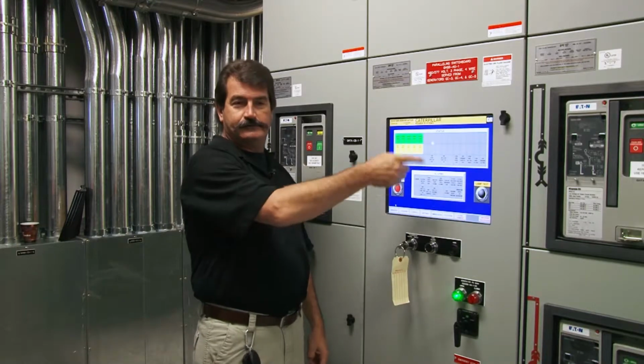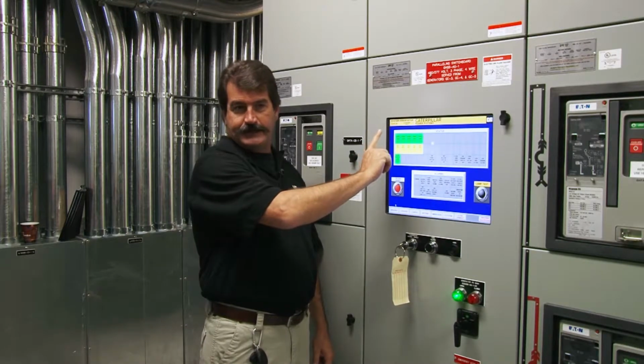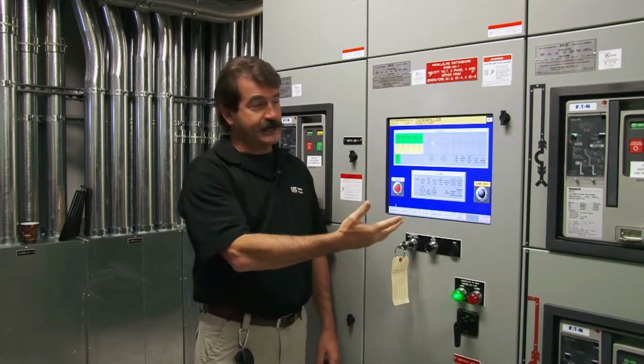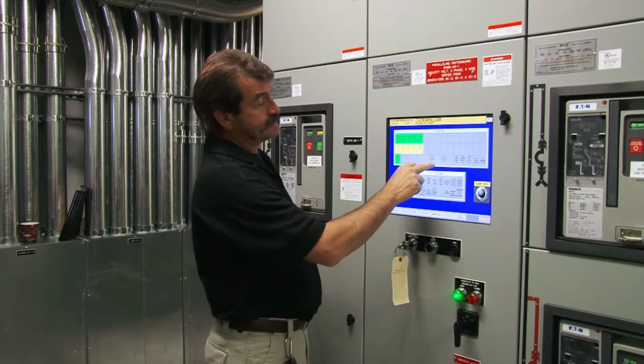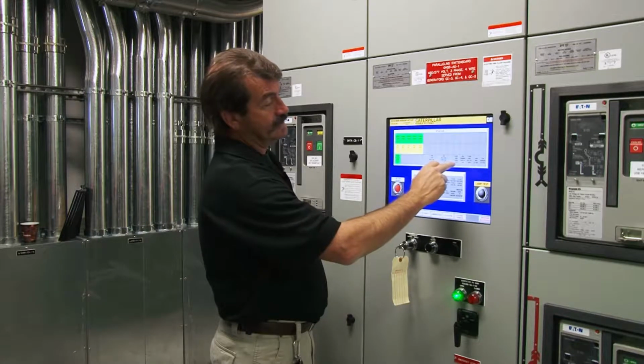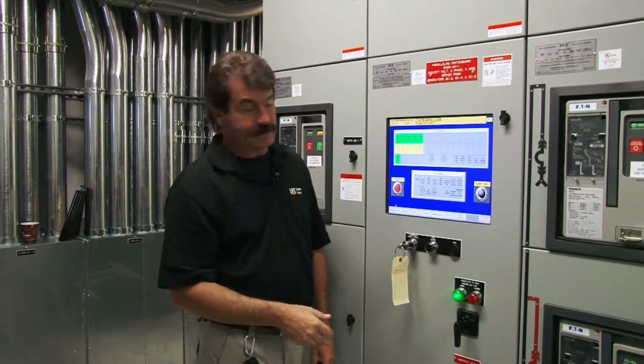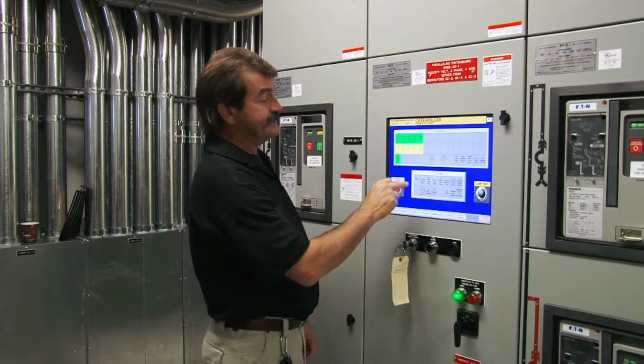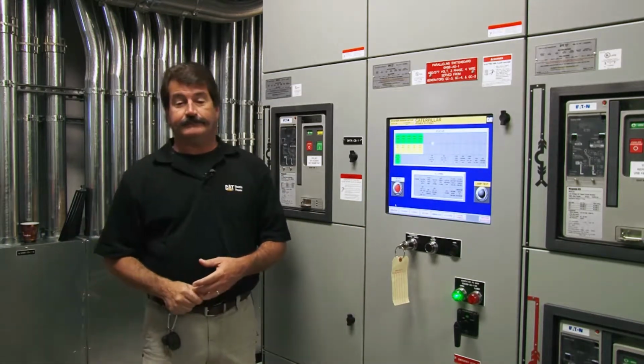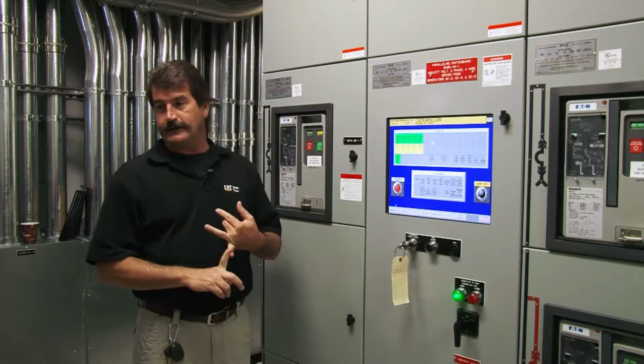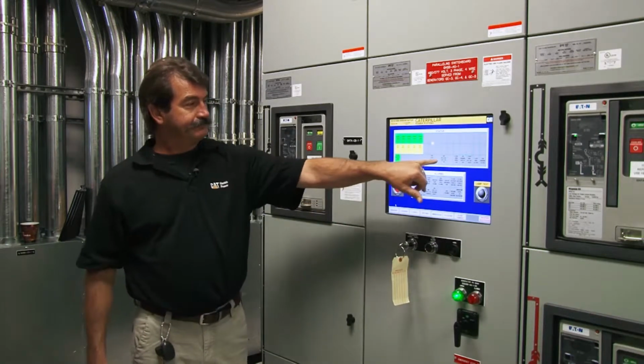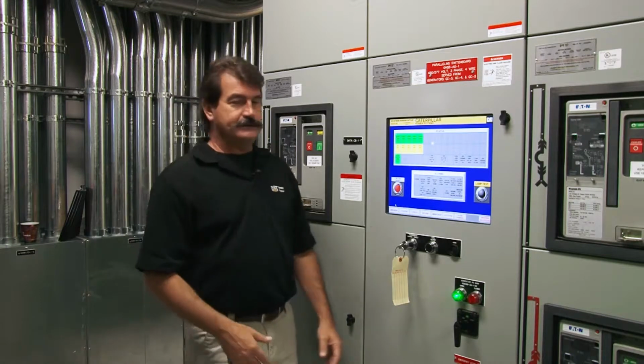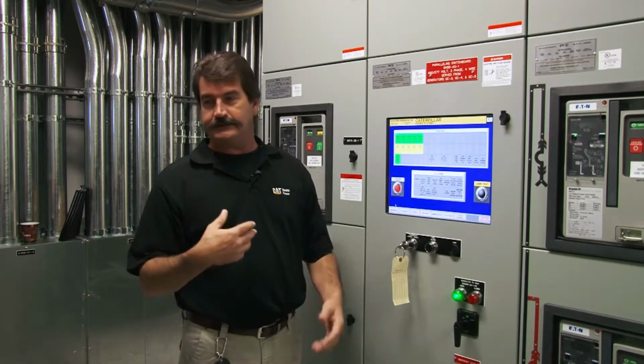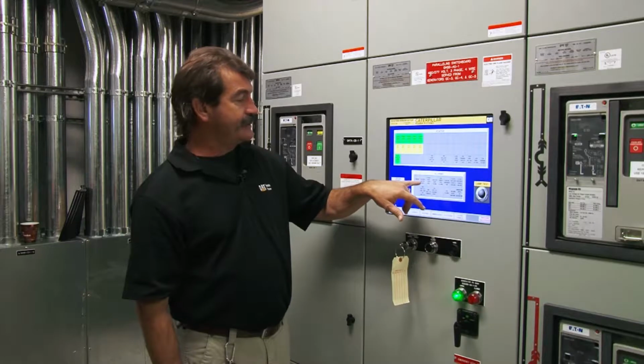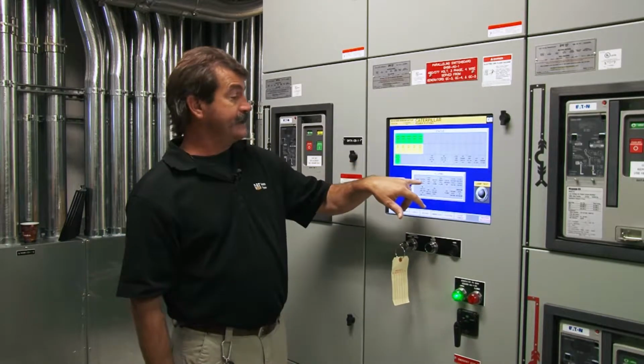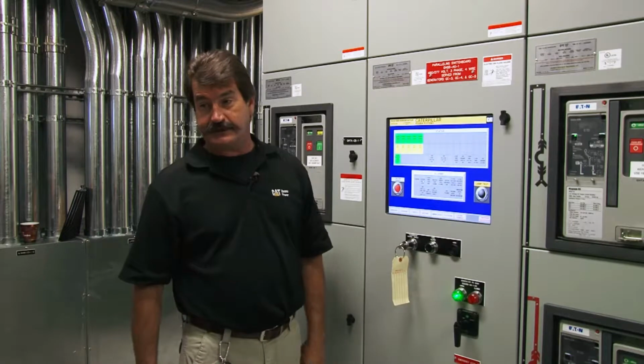Master mode switch is in auto. Whenever I moved it to manual, that showed up as red and it said manual, okay? There's your load test switch, your no load test switch. All these right here are just statuses of what you've got going on there. Big alarms, E mode. E mode means that the gens are running on the bus, and not in no load test, okay? That they've got a run signal from an ATS is what that means. System not in auto, the only way you can get that, actually you can get that by having your circuit breakers not in auto too.